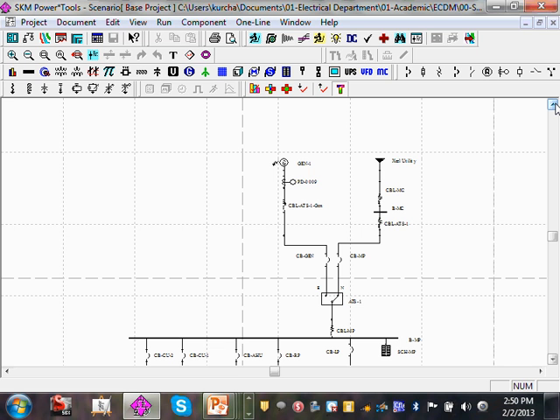So when we have a circuit breaker, it has to have three things, or a fuse. You have to have three things about a circuit breaker or fuse. Number one is the voltage. Is the system 480? Then typically we either buy a 480 circuit breaker or fuse, or 600 volt. 600 volt can handle 480. The voltage. So if you put a circuit breaker on a voltage that's higher than what that circuit breaker can handle, you will expose it to more stress and it will malfunction.